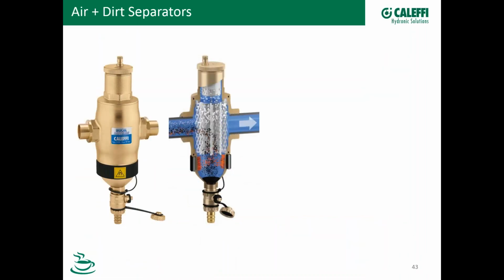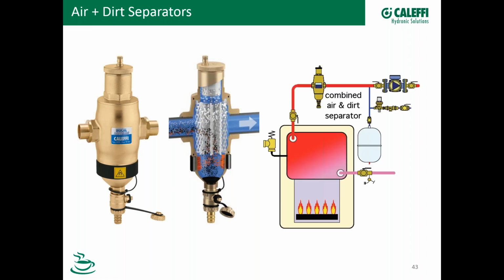Caleffi also makes air and dirt separators. So this is a combo unit. The picture we're showing here is called a Discal Dirtmag. And if you look at the upper half, this top half of the Discal Dirt, it's an air separator. Everything is the same from here up. And what we've done is added dirt separation in the same housing. So this is a 2-in-1. This particular one has magnetic dirt removal and dirt removal down here and a purge valve on the bottom.